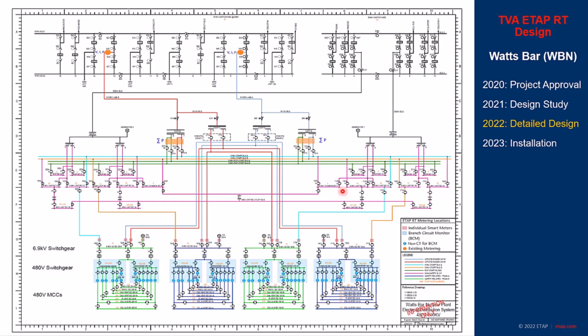However, to get all the sensors I need in partnering with ETAP, we figured out we're going to need to put some smart meters, and that's what these red squares are here. So there will be one smart meter on each incoming circuit at our 6.9 kV shutdown board switchgear. And then we're also going to have what we call branch circuit monitors, and I'll show you a little bit more detail on that, but there's 8 of those. So there's one for each 480 volt switchgear. Here's 8 switchgears, and there'll be 8 branch circuit monitors.